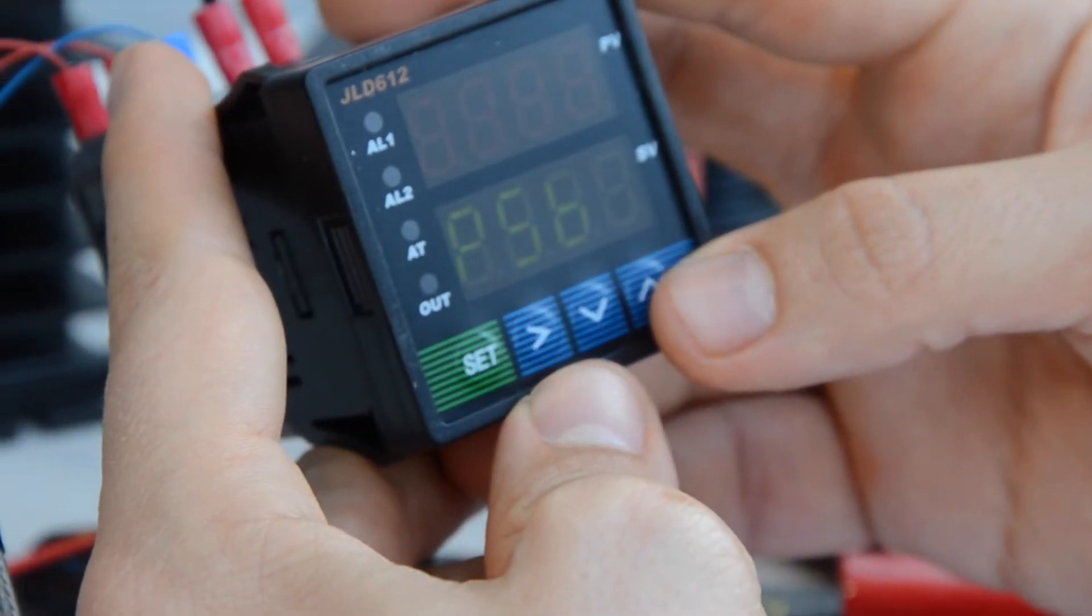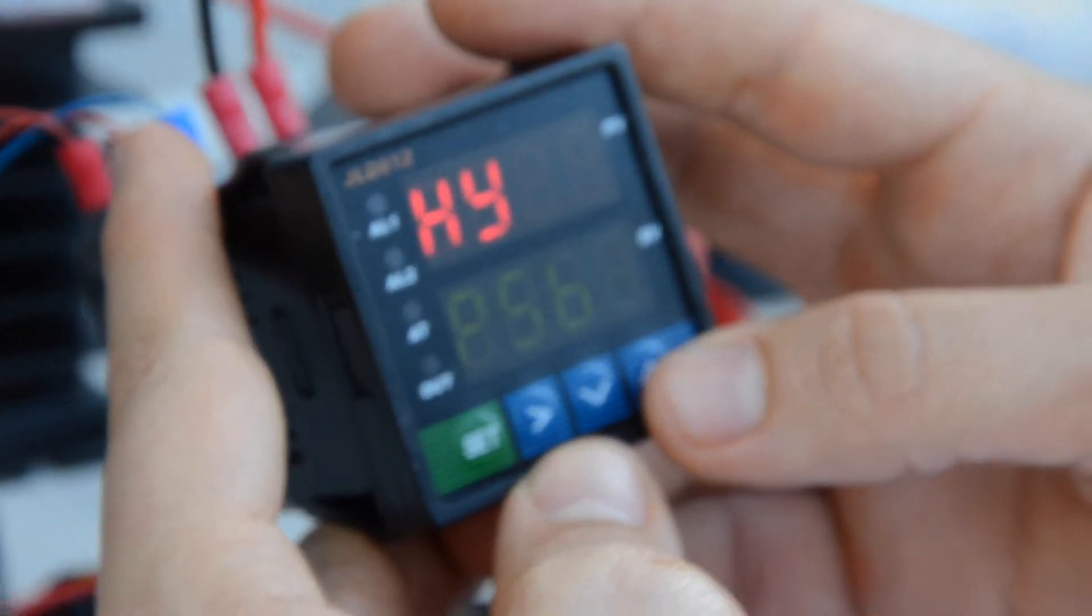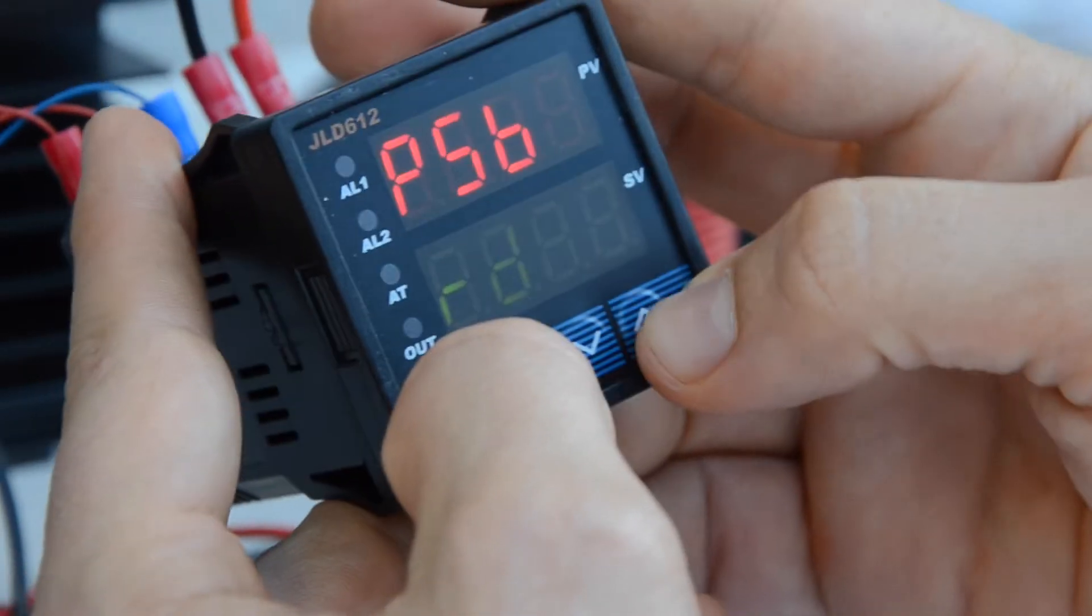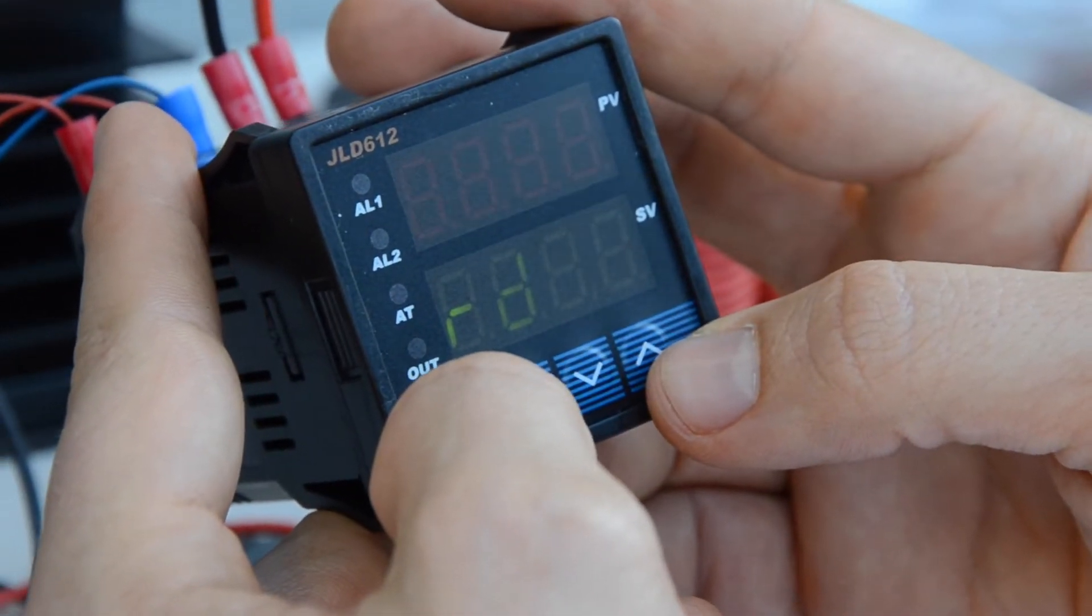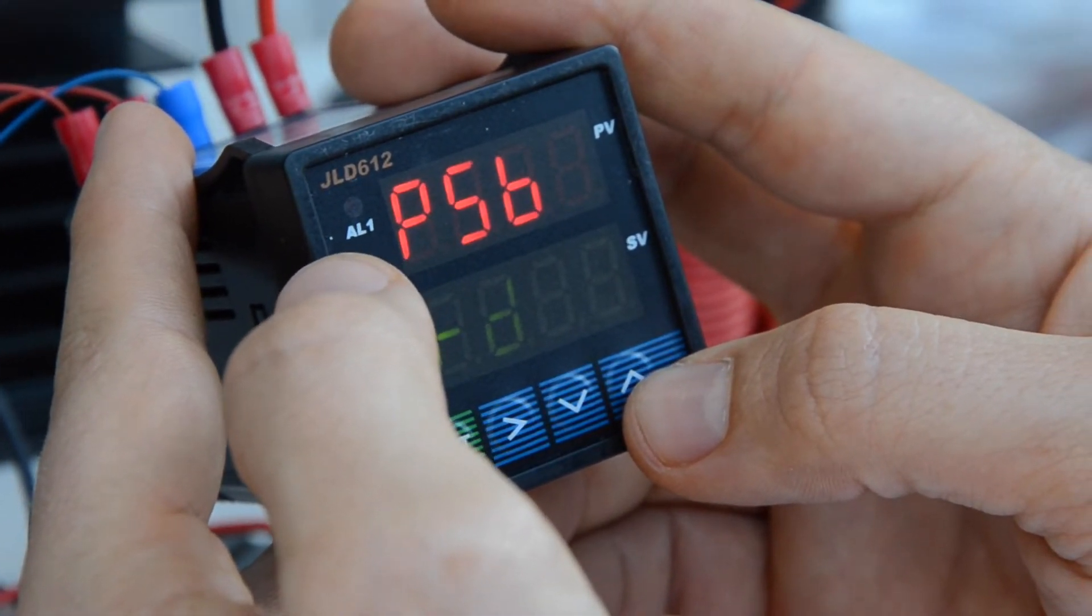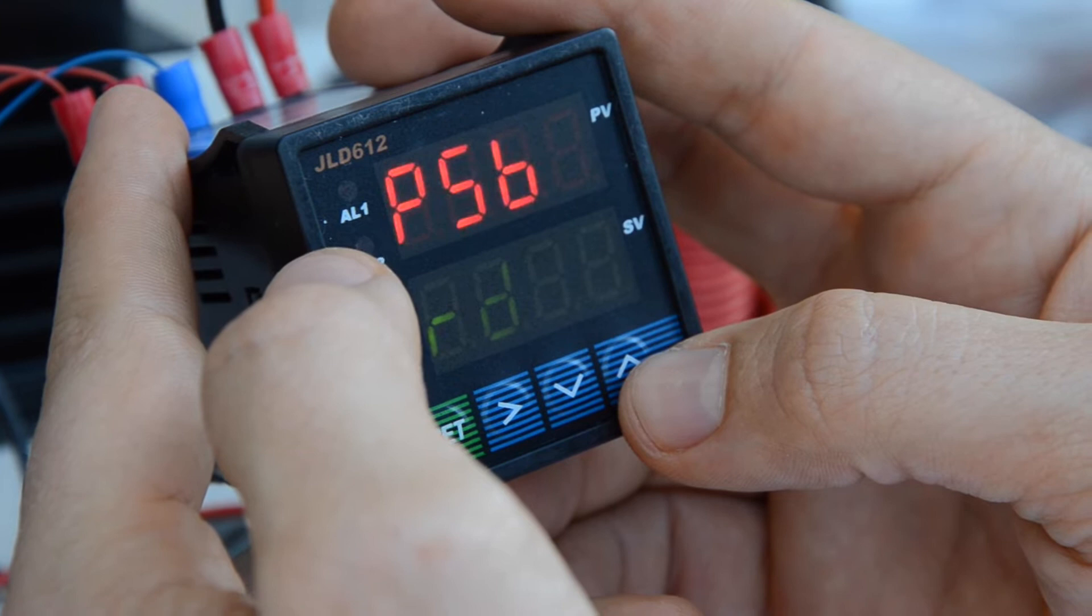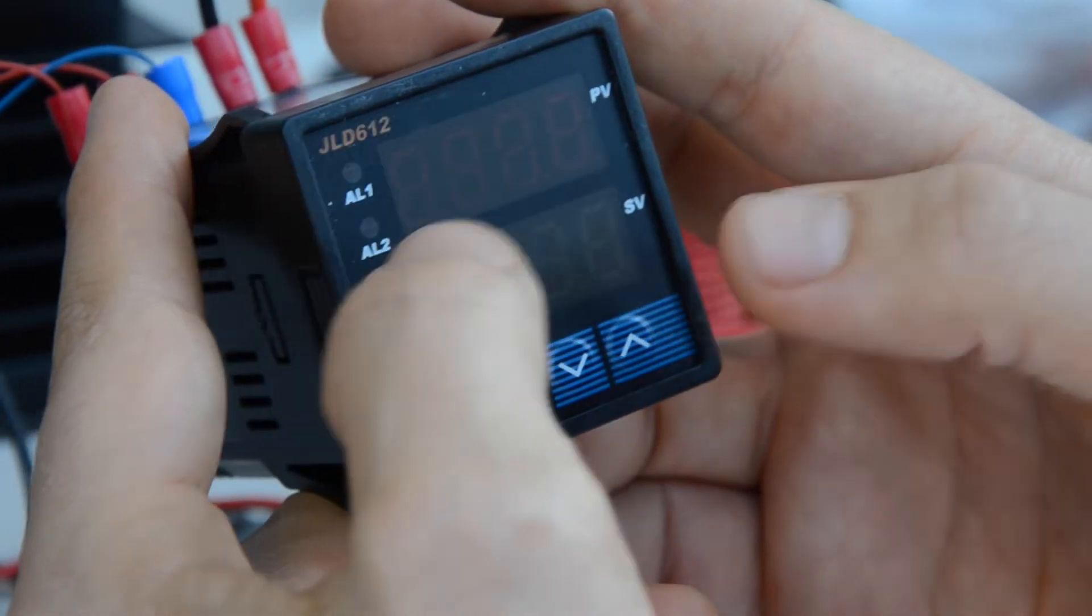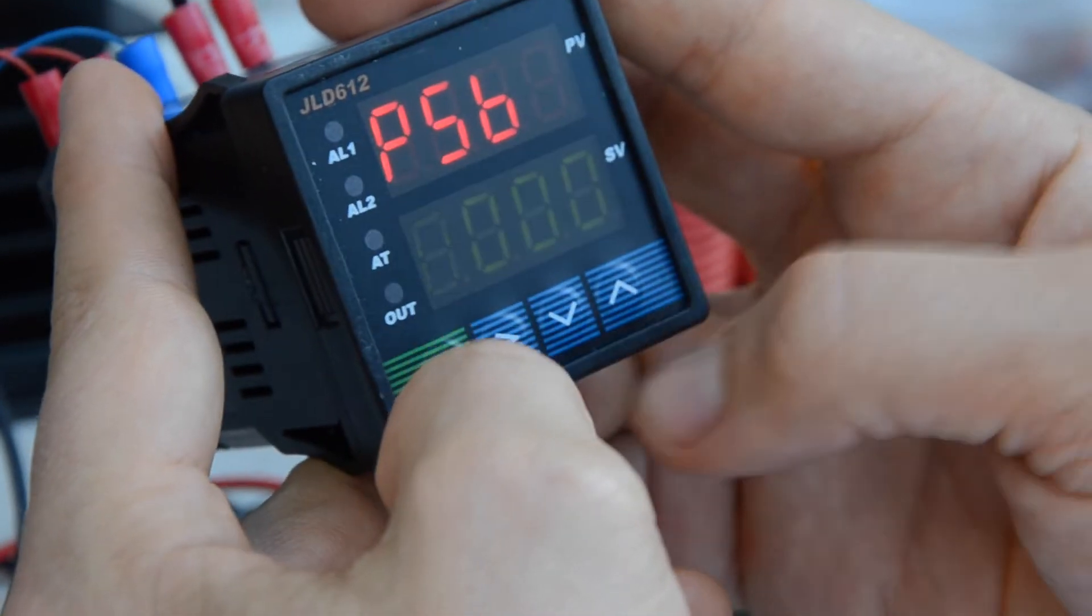So we'll set that one. Going up to the next one, HY, we left at the default setting. For the next one, this PSB, we also left at the default setting. This one specifically corrects if you have a thermocouple that may be reading one or two or three degrees off and you measure it with a better thermometer, you can adjust that by moving it plus or minus.